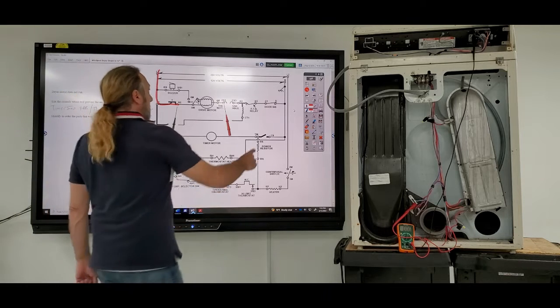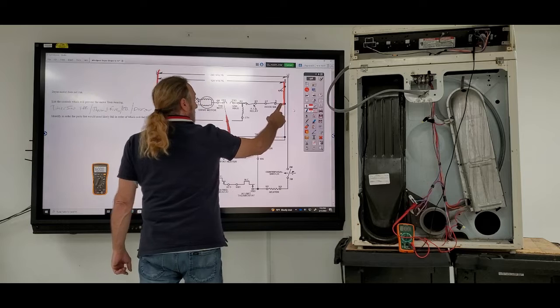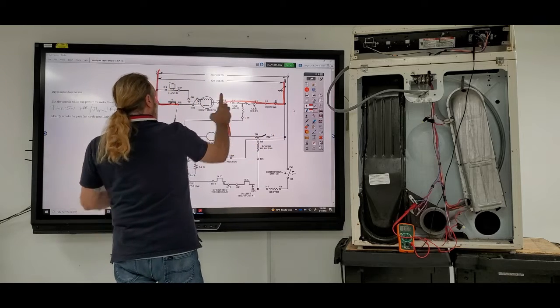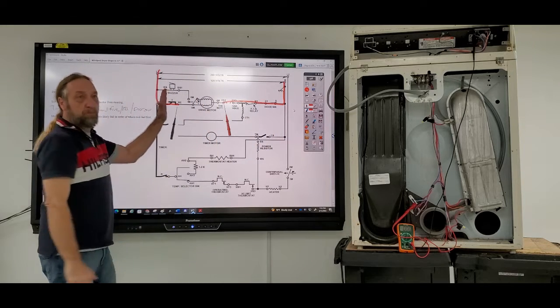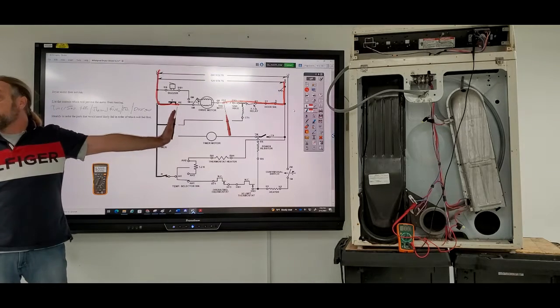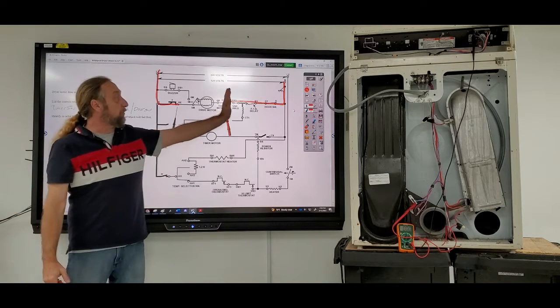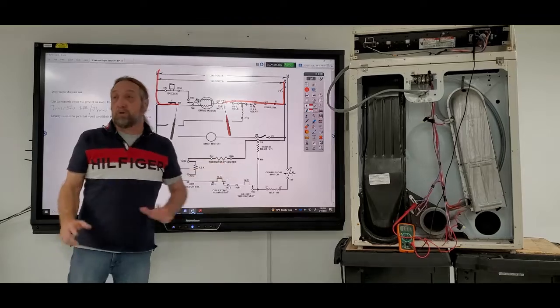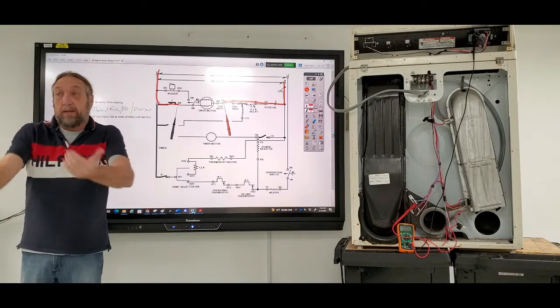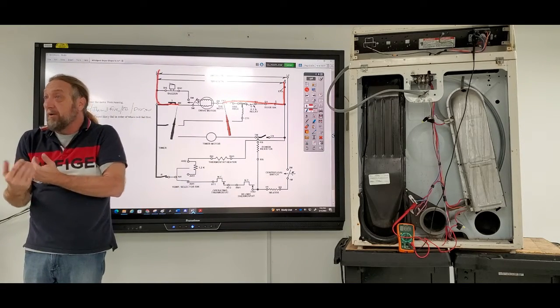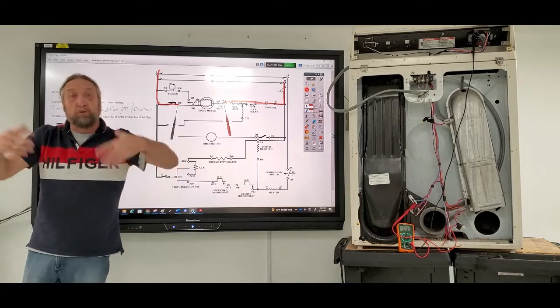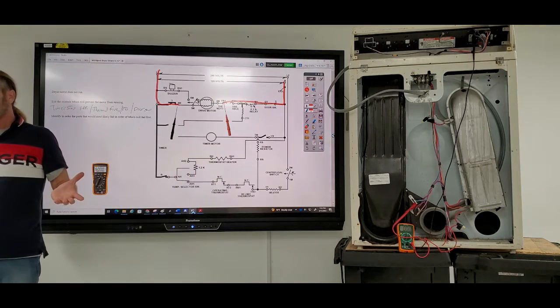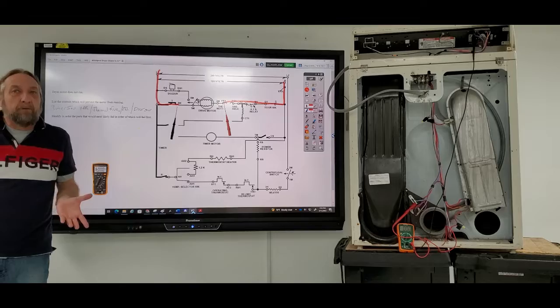Neutral. Neutral is all the way to this point. If this timer was broken, line 1 would not be on the black meter lead. If this fuse was bad, or the start switch or the door switch was bad, I wouldn't have the neutral on the other side of the meter. If either side was broken, I wouldn't have a voltage reading.